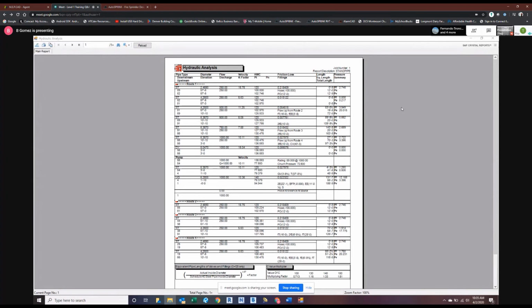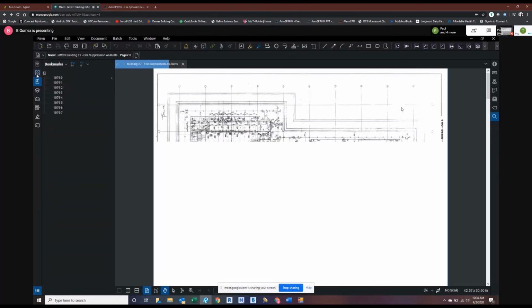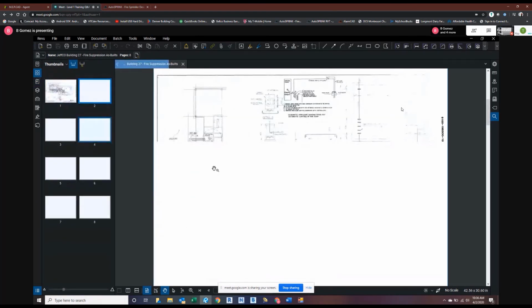I've dealt with fire authorities that say, oh, you're replacing the fire alarm control panel, we'll bring everything up to code. If you replace one device, that's fine, everything can stay, but you replace the brain of the system, and the fire pump, man, that's it. That's the thing that's doing all the work. So just some tools to put in your tool bag to use when having conversations with pump reps and fire authorities, of considering what would be appropriate for this scenario.